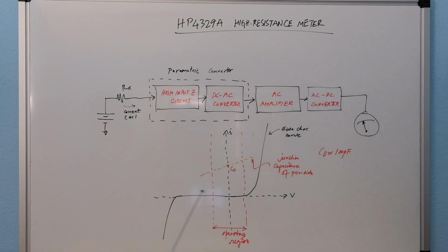Either low or high resistance, it does not use choppers or other kinds of circuits to remove offsets and drifts and so on. This uses a completely different approach, what they call a parametric converter. I'll go into the details, but essentially it consists of a bridge in the input stage, which converts an input current from an unknown resistor, and the current is then converted to an AC signal, which is amplified and then converted back to DC to display on a meter. There's also feedback involved to balance the bridge, in the sense that it actually creates oscillations, but the principle is quite interesting, and I can discuss that in detail.